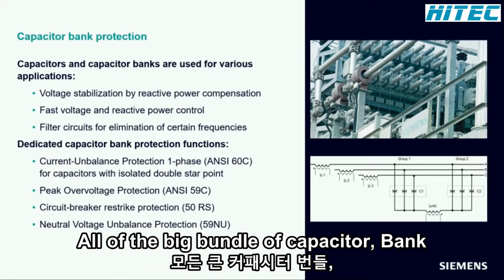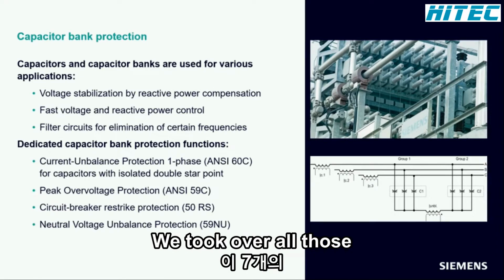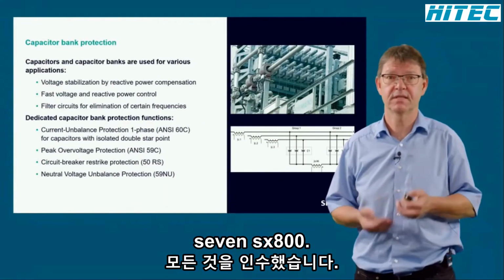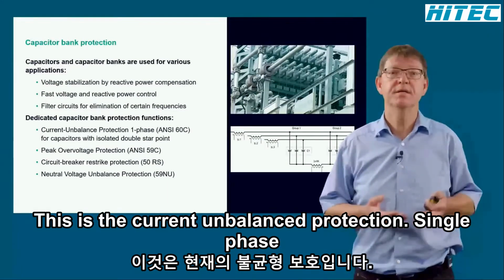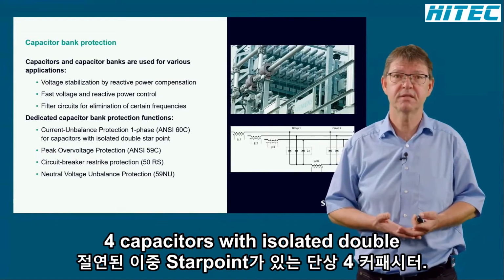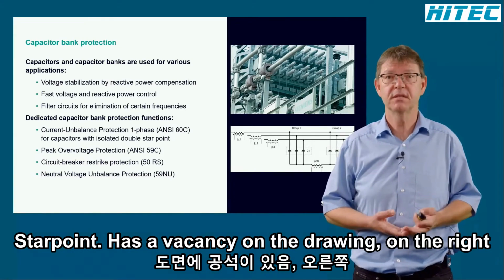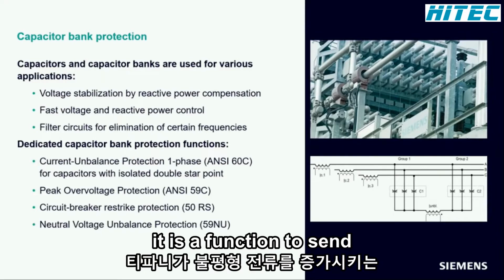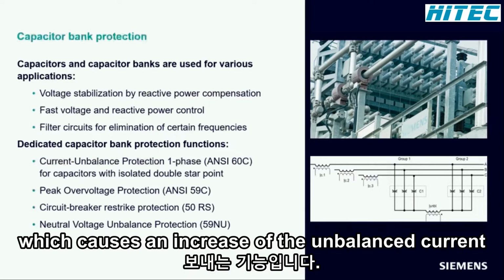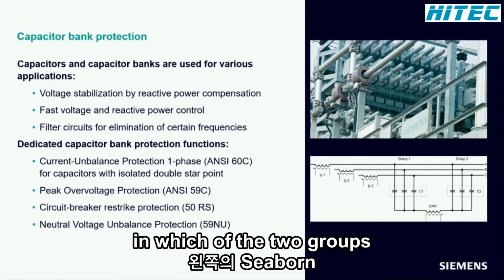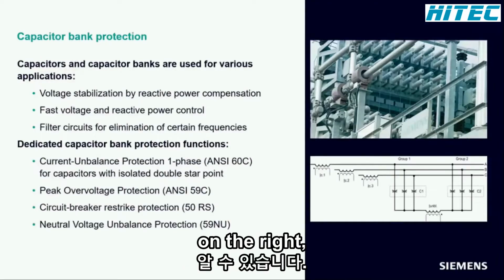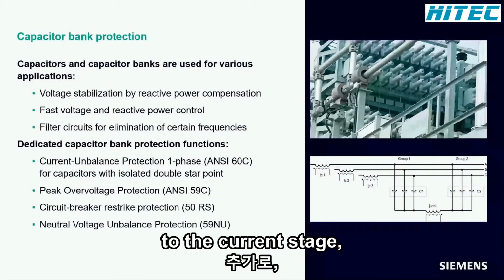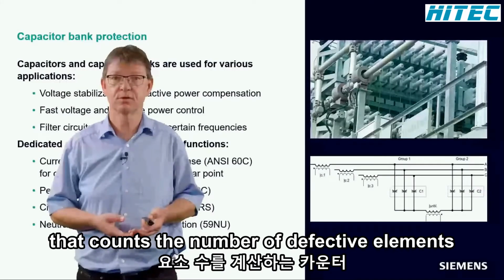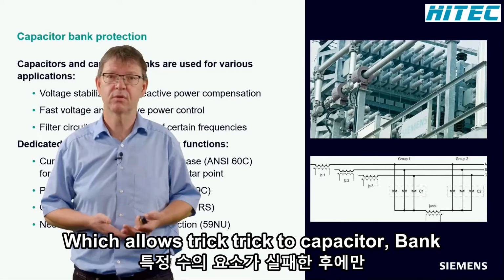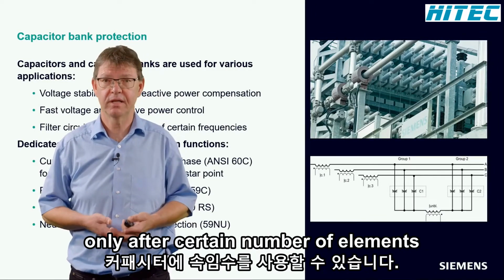Out of the big bundle of capacitor bank specific functions SIPROTEC 5 offers, we took over all those which can be handled with the hardware setup of the 7SX800. This is the current unbalanced protection single phase for capacitors with isolated double star point, as you can see on the drawing on the right hand side. It is a function to sensitively detect failures of single capacitor elements, which causes an increase of the unbalanced current. The orientation of this current allows to find out in which of the two groups, C1 on the left or C2 on the right, the fault is located. Additionally, to the current stage, the device provides a counter stage that counts the number of defective elements in each group and which allows to trip the capacitor bank only after a certain number of elements have failed.